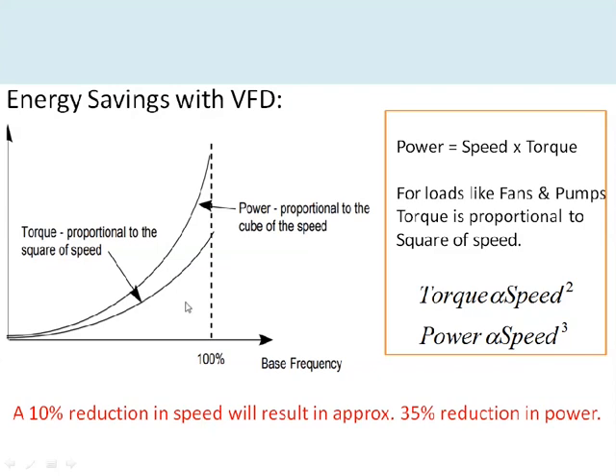Energy savings are most evident in loads like fans and pumps, where torque is proportional to the square of the speed. Since power equals torque times speed, power is proportional to the cube of the speed. In these applications, a 10% reduction in speed results in a very drastic reduction in power — approximately 35% reduction in power can be achieved. This is where the VFD plays a vital role in energy savings; if the application does not require base speed, you can operate at a lower speed for significant energy savings.